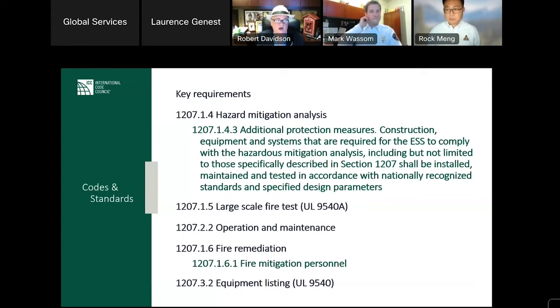Both 855 and the fire code speak to large-scale fire tests, and there's an assumption, recognizing that a properly installed system should not go into spontaneous thermal runaway. We also recognize that other things could occur to damage the system and cause that catastrophic failure. Okay, what are we going to have? What are we going to deal with? And more importantly, a portion of that test is that one unit can burn up and not propagate to the others, because we're not going to be able to put them out.